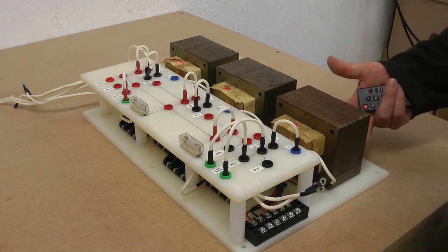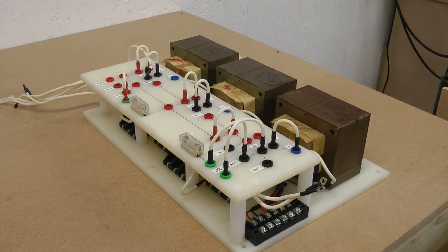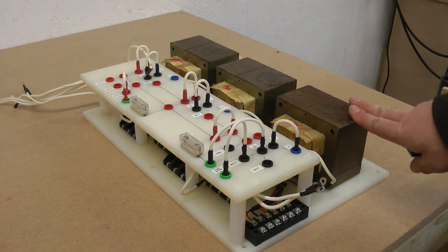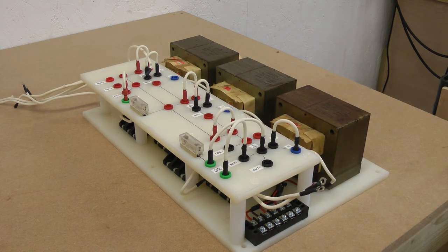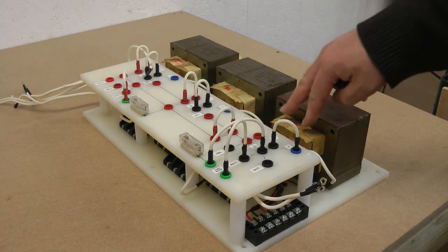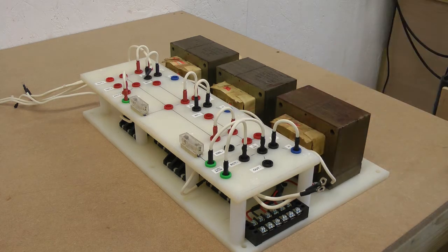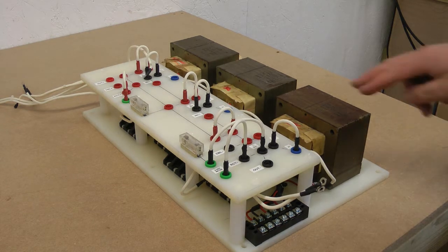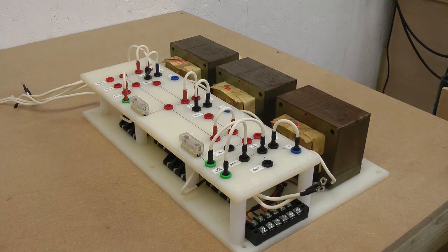You introduce a magnetic loss there with those shims, and that, when coupled with the impedance of the magnetron, means that even when you apply maximum line supply to the primary, you are essentially getting the right power output from the secondary, which is, in this case, of course, limiting. We want to make full use of the power capabilities of the transformer right up to its top end performance, and to do that we need to knock out the shims. That does mean that you need power control.